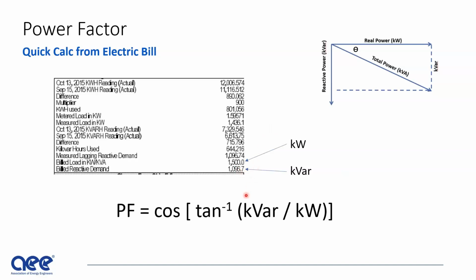In terms of a quick check on power factor, you could look at a bill for a customer. You see in this case, the kW is 1500 and the kVAR is 1096.7. On your calculator, we know the angle here is going to be the kVAR divided by the kW. Take the arctangent of that quotient and take the cosine. The arctangent of this value is theta, this angle up here, and the cosine of theta is your power factor.